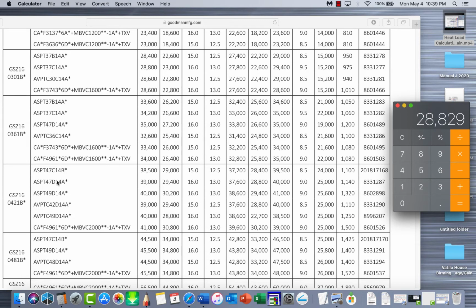This is indoor coils. There's multiple indoor coils with different setups, maybe a TXV, an AXV, an orifice, an electronic expansion device. But these are the different coils that you can match up to them. So you got 1, 2, 3, 4, 5, 6, 7 different coils that can match up to it. But you see the sensible loads on these are all different. So which one do we need to meet? Well, we would want to get the one that's closest to the number that we got. Like I said, there's 29,000 here.